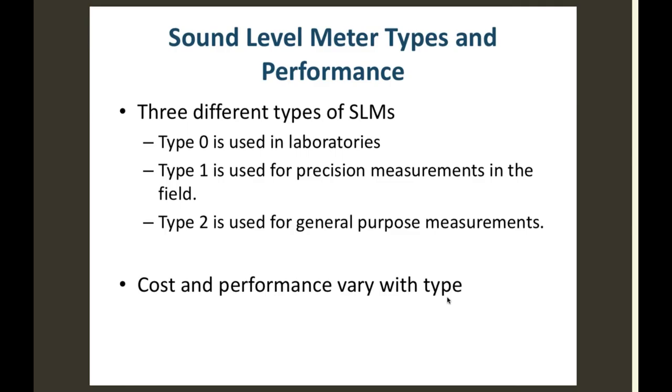So if I want to start doing a survey in here, what's the first thing I have to do with this thing? Bingo. Thank you very much. Okay, excellent. I have to calibrate the thing, right? So we have devices for calibration. This basically is a little sound production device. If you read right down here, it says that it produces 114 decibels at 1,000 hertz. So when I turn this switch on, can you guys hear that from back there? Right, when I turn the switch on, you can actually hear this making noise.